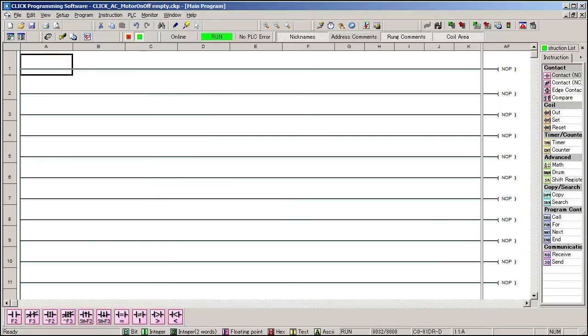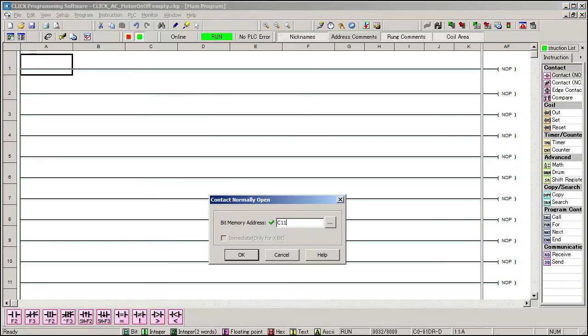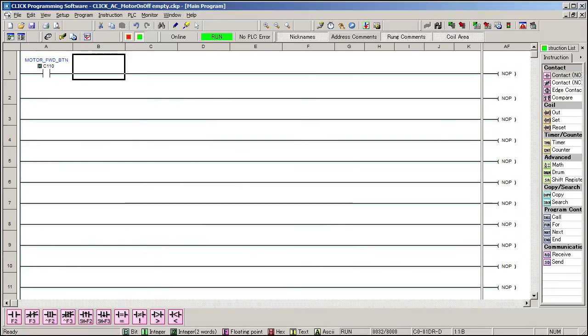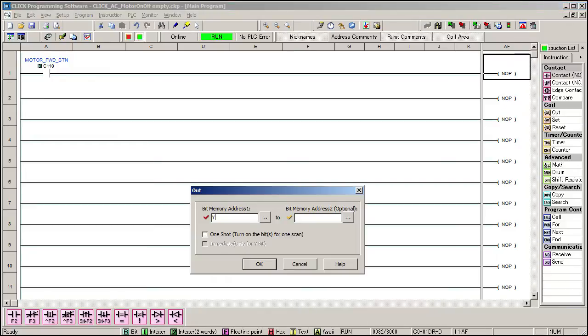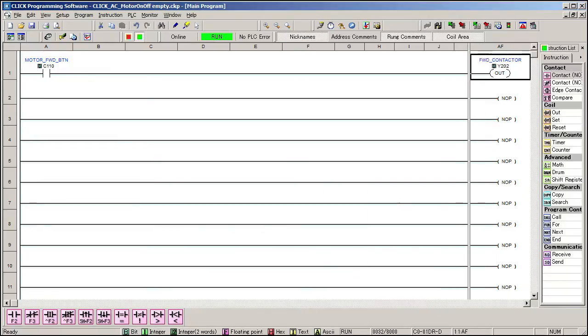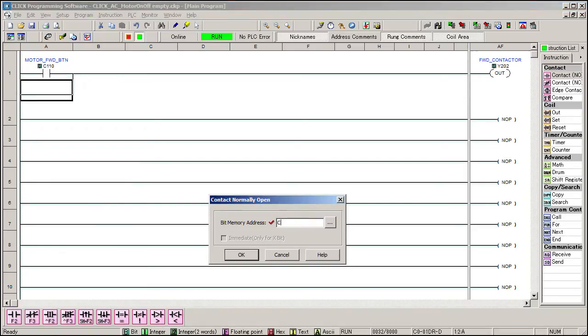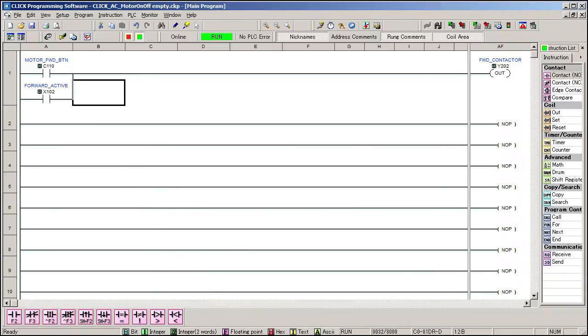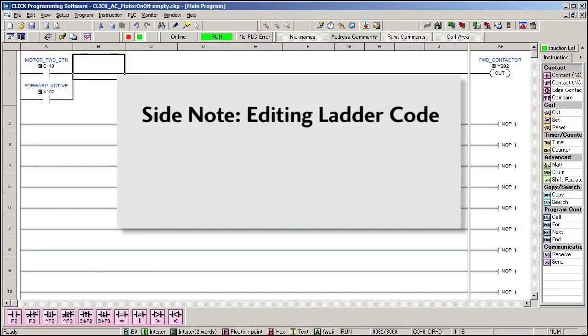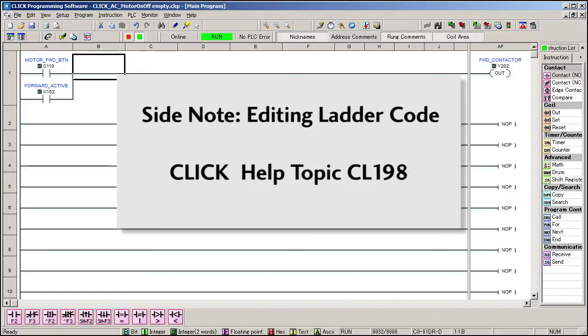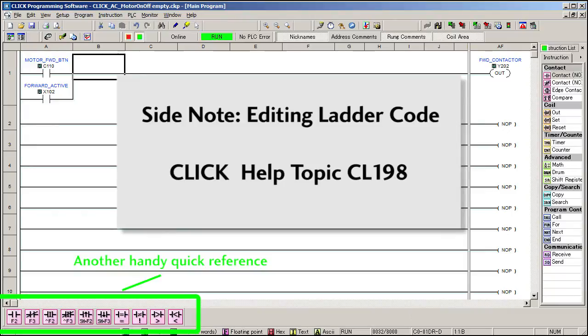Let's get the motor running in the forward direction. So on a button press, our virtual C-more HMI button in this example, enable the forward contactor which is output Y202 in our setup. And once that forward contactor is engaged, the AUX contact closes so we can use that to keep the motor running even after the momentary forward button is released. We call this sealing or latching the contact. Now I should mention that we will be using a lot of shortcuts to expedite the typing of this code. So if something appears on a rung and you're not sure how it got there, then check out Click Help Topic CL198. It lists all the keyboard shortcuts.